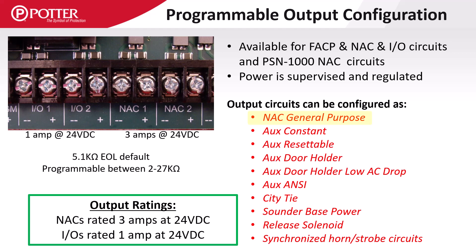NAC General Purpose is a reversing polarity notification appliance circuit that does not include synchronization. A circuit programmed as this output type is best suited for a device like a 24-volt bell. When set for AUX constant, the circuit provides uninterrupted 24-volt DC auxiliary power. AUX resettable is a constant 24-volt DC output that momentarily turns off when the panel is in a reset cycle.